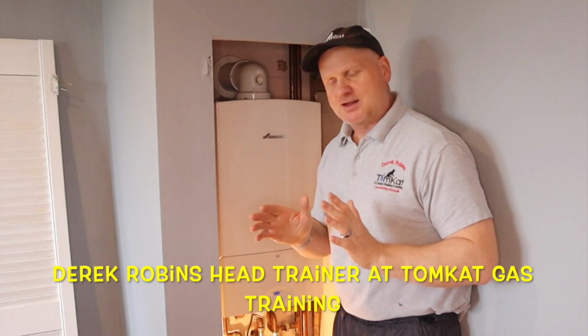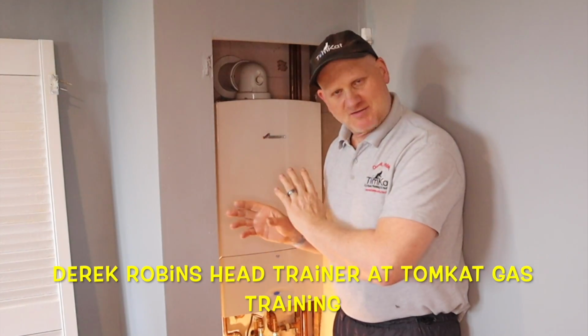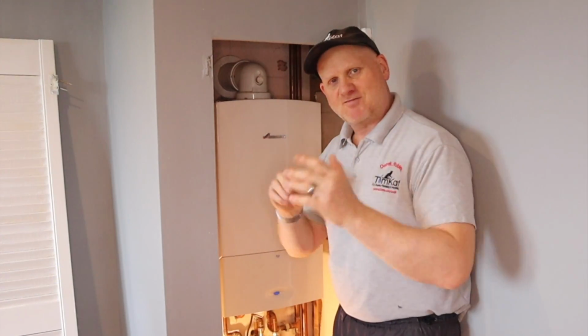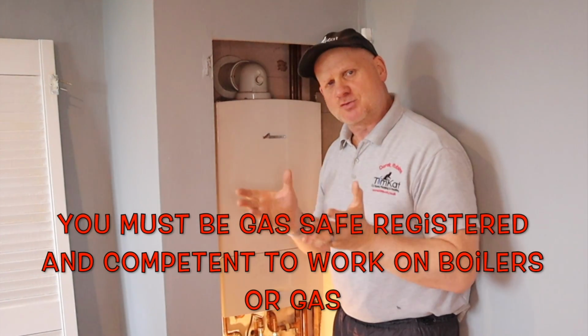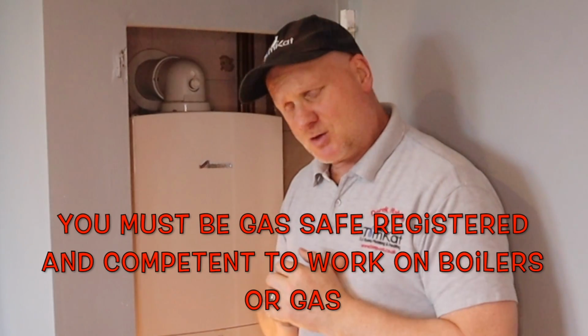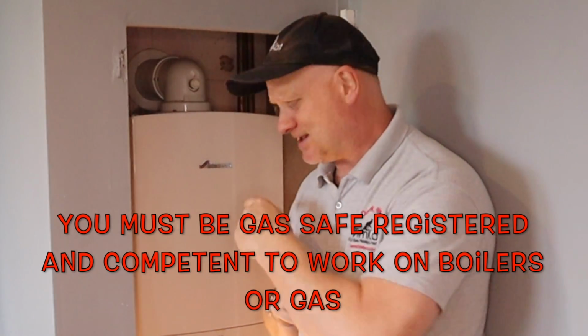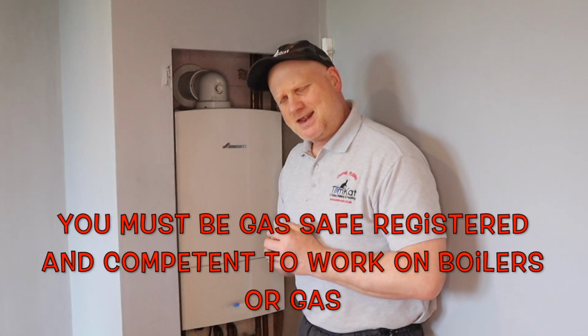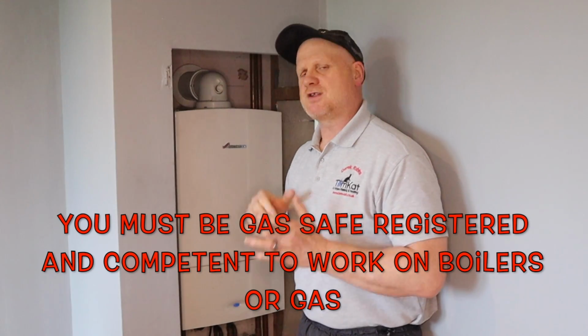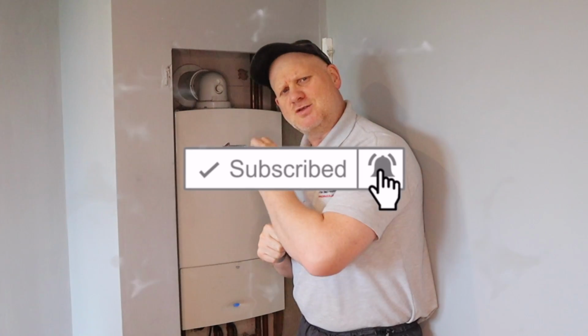Now, the first thing we need to do before we actually service the boiler is a safe to touch test and a visual inspection, because we don't know whether we're going to get electrocuted or not touching this cover. Now, we've only been in this house for about 2 weeks now, and this is the first chance I've actually had to look inside this boiler. It has been giving us a few problems and keeps locking out. So let's get on with it and do this visual inspection and the safe to touch test.